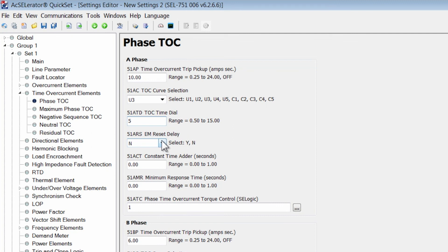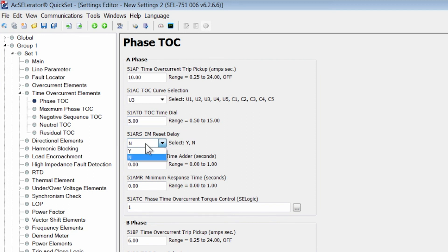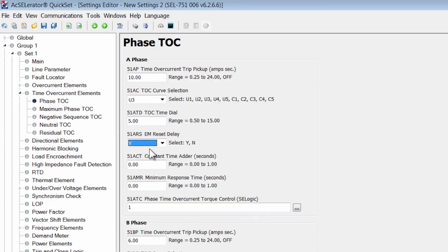The electromechanical reset delay is important to consider when you're doing a coordination of multiple relays such as microprocessor relays with electromechanicals. Because the reset time of electromechanicals is based on an electromechanical delayed reset, you would also want to enable the electromechanical reset feature in the 751 relay. So let's assume we're coordinating with other electromechanical relays that have been installed. So we set the setting to yes. These are the basic settings that it takes to configure a 50 and a 51 element.